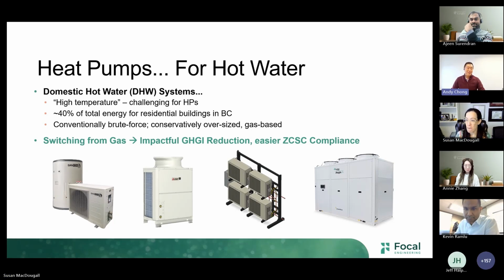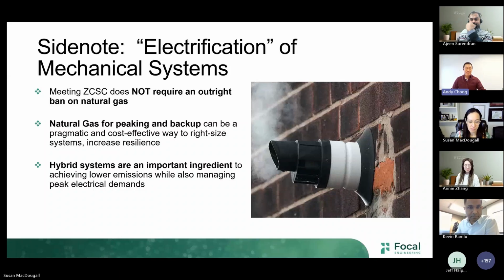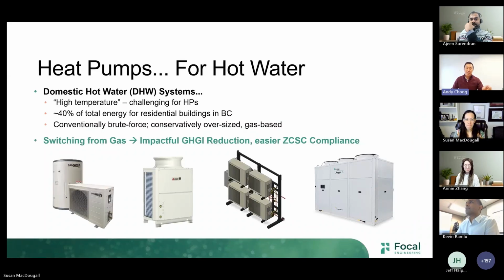You triggered another thought for me. I don't have a slide on this, so you'll have to use your imagination a little bit. If I can go a level deeper on heat pump water heating - something else I've learned applying these systems and speaking on this topic in other venues - I think we need to stop thinking about hot water as this instantaneous thing. It was very fashionable for a long time for people to call gas water heaters instant water heaters or tankless water heaters. Frankly, it was very good marketing. But if it generates hot water instantly, and it's 120 feet away, you're still waiting 45 seconds at your faucet, so it's not instant.